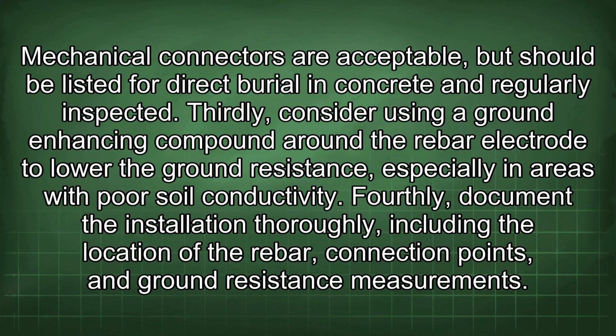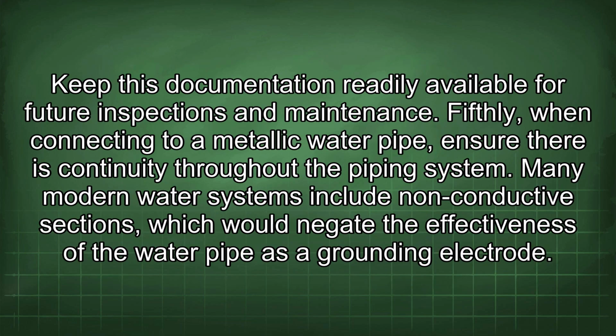Fourthly, document the installation thoroughly, including the location of the rebar, connection points, and ground resistance measurements. Keep this documentation readily available for future inspections and maintenance. Fifthly, when connecting to a metallic water pipe, ensure there is continuity throughout the piping system. Many modern water systems include non-conductive sections, which would negate the effectiveness of the water pipe as a grounding electrode.